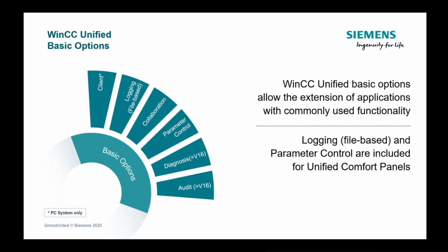Another basic option we have is collaboration. This is unique to WinCC Unified. The concept of collaboration allows different WinCC Unified systems to collaborate with each other. So we could have a WinCC Unified system on a PC and one on a panel, so two different systems. And through the concept of collaboration, they can share screens, tags, parameters, archive. So you don't have to go and engineer that, you just license it, and then you have the ability to share or collaborate in runtime.